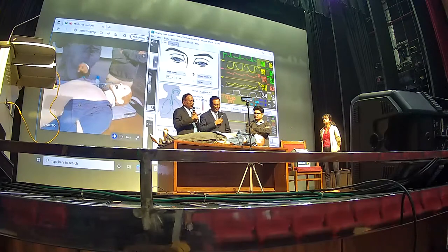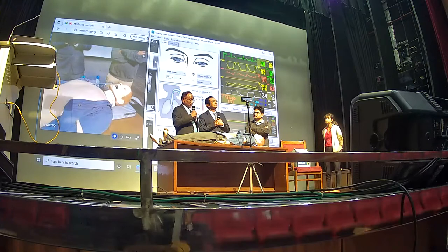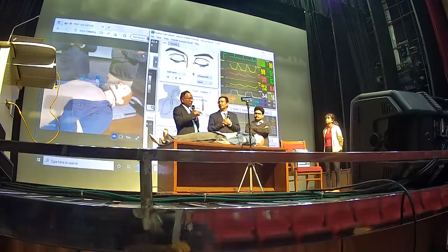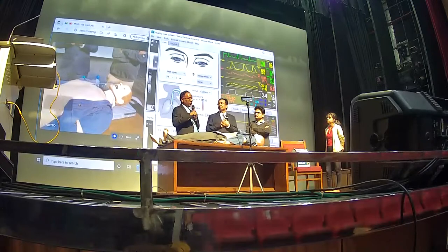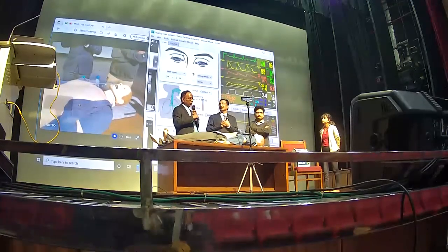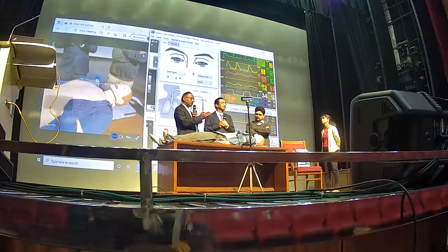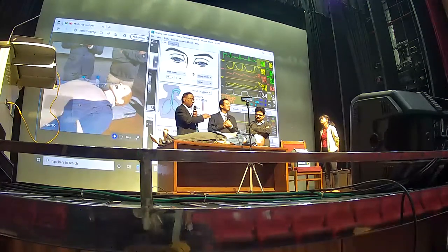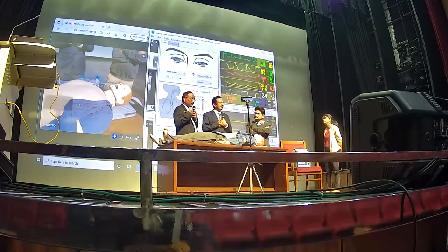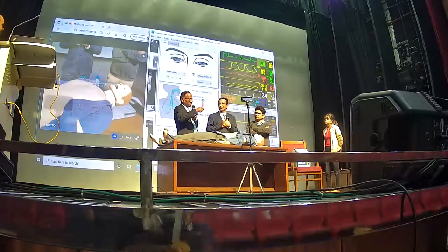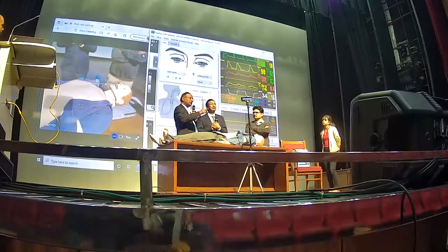To answer that question, many centers in the world I've visited do the apnea test not by disconnection of the ventilator. They do the apnea test with the patient on CPAP. But the unfortunate thing with most of the CPAP ventilators available in our country is that they go into the backup mode after 20 or 30 seconds, and the patient will be shifted back from CPAP to SIMV. You understand? If the backup mode can be turned off, there are Dräger ventilators available. I myself tested it in Italy, where I was recently. So if you can turn off that backup mode in CPAP, then you can do the test with the CPAP mode.